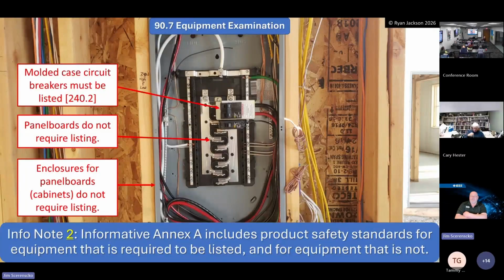And then they do have that exception that says you can put it on the packaging. Now it's got to the point where most of the equipment has barcodes on it, or a QR code. So you go up with your phone. My inspectors can go up to a circuit breaker now, hold it up to the QR code, and it pulls up everything from Siemens or Eaton or Square D, or not to leave anybody out, GE, whoever, and it brings up the whole spec sheet of the breaker. So kudos to the QR codes.